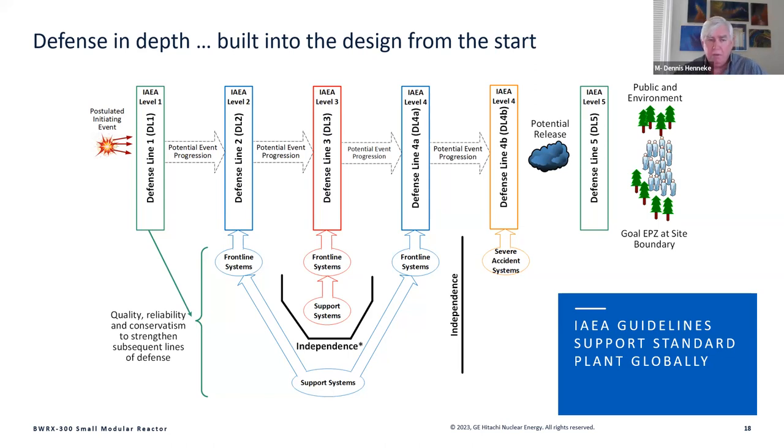For example, if you have an anticipated operational event, an AOO, you should have a defense line 2 system that prevents the operation of a defense line 3 system, which is your safety-related system. It's not a shall statement, it's a should, and we try to implement it in that regard. If you have a lower probability or frequency event that may be, say, in the DBA range, there is not a requirement to have a defense level 2 system.